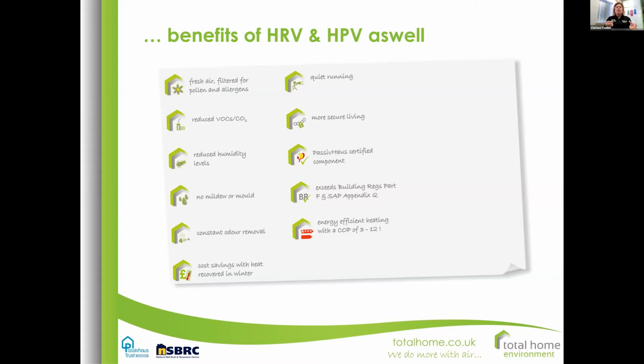Now with a gas boiler, you're putting a kilowatt of energy in, you're only going to be getting 900 watts out. So you'd be saying, well, where's my 100 watts? Thank you very much. So with 1 kilowatt of energy, you're getting at least 3, if not 12. Now, obviously the 12 is going to be ideal scenarios, but typically with this sort of system, it will be 5 or 6. So really good energy efficiency there, much, much better than coal, etc.